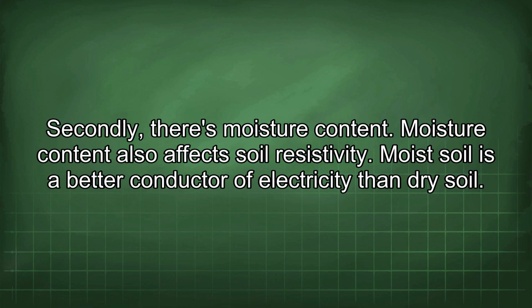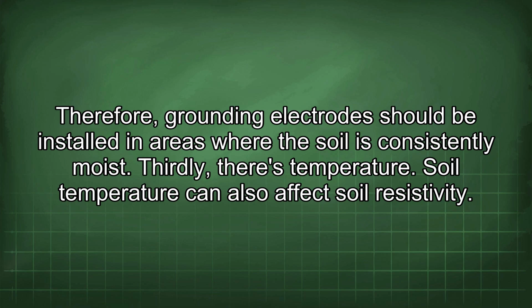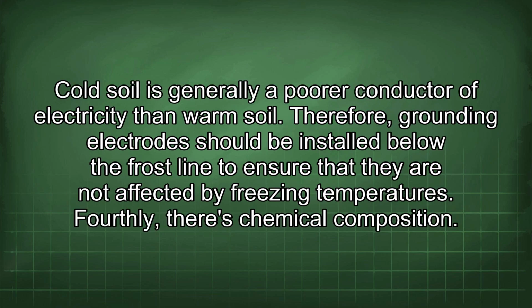Moisture content also affects soil resistivity. Moist soil is a better conductor of electricity than dry soil. Therefore, grounding electrodes should be installed in areas where the soil is consistently moist. Thirdly, there's temperature. Soil temperature can also affect soil resistivity. Cold soil is generally a poorer conductor of electricity than warm soil. Therefore, grounding electrodes should be installed below the frost line to ensure that they are not affected by freezing temperatures.